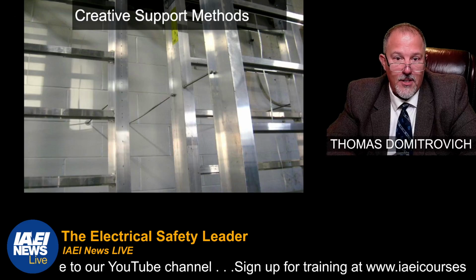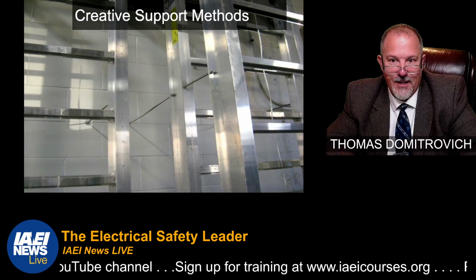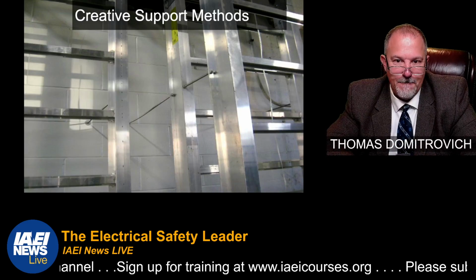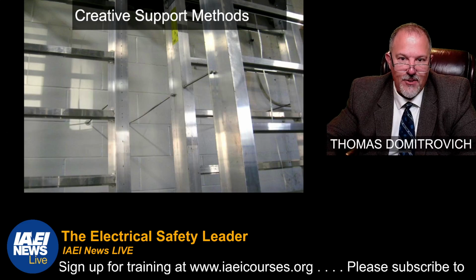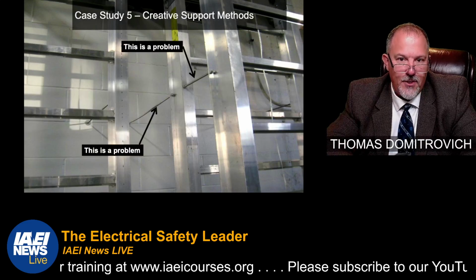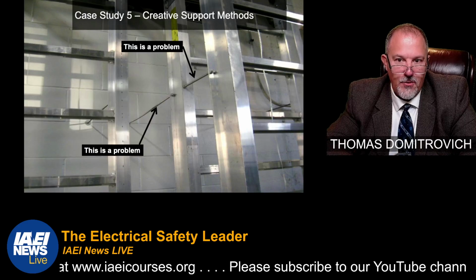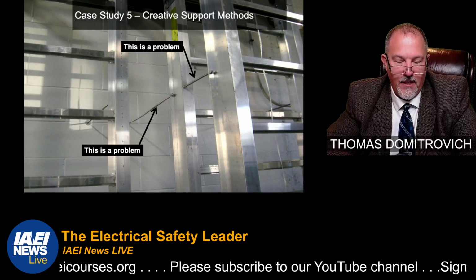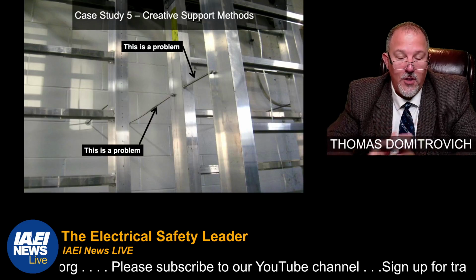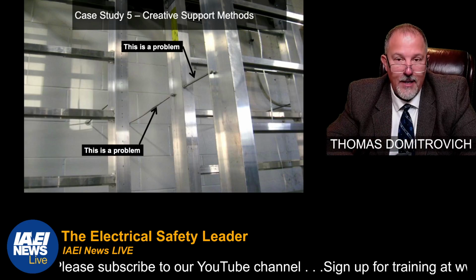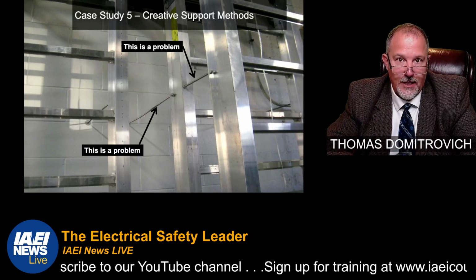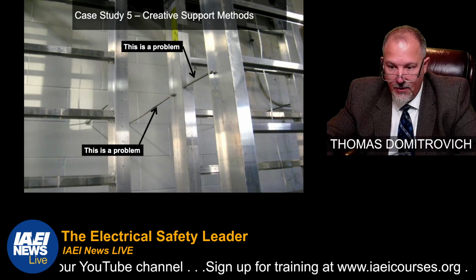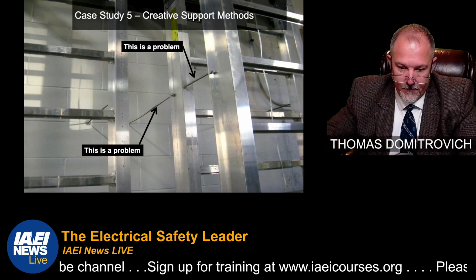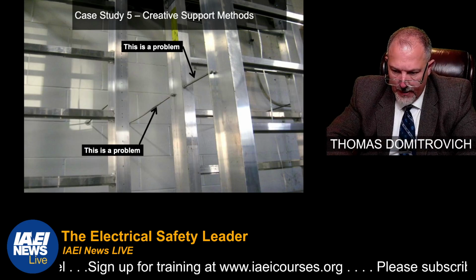Here's another. This is a creative support method that was employed at a facility that was not per manufacturer's instructions. Those are problems. Use the listed equipment. Follow manufacturer's instructions. Use equipment that are identified for the purpose for that installation by the manufacturer. They'll tell you how to support the installation.